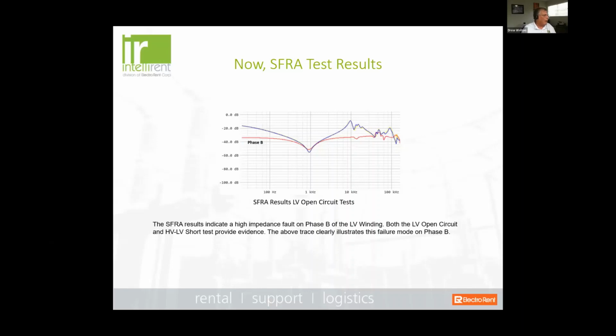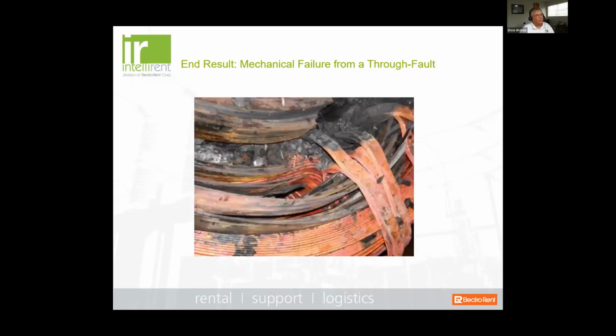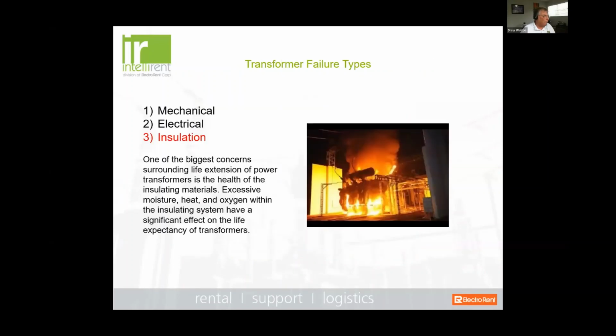Now, if we look at our SFRA results, this indicates a high impedance fault on phase B on the low voltage winding. And remember what we said about where through faults give you an indication on your SFRA. It's in that low voltage winding. So both the low voltage open circuit and high voltage to low voltage short circuit tests provide this evidence. Okay, so this clearly illustrates a failure mode on phase B. And this is what we saw when we detanked the transformer and tore it all apart. Serious mechanical failure resulting from a through fault.